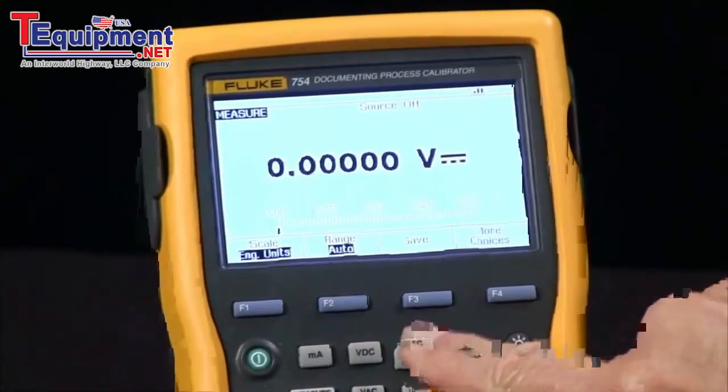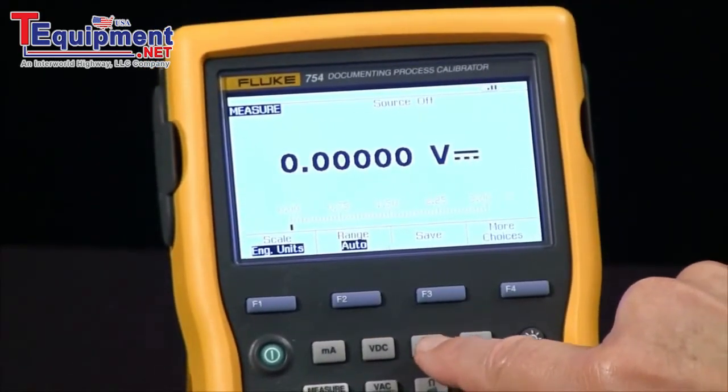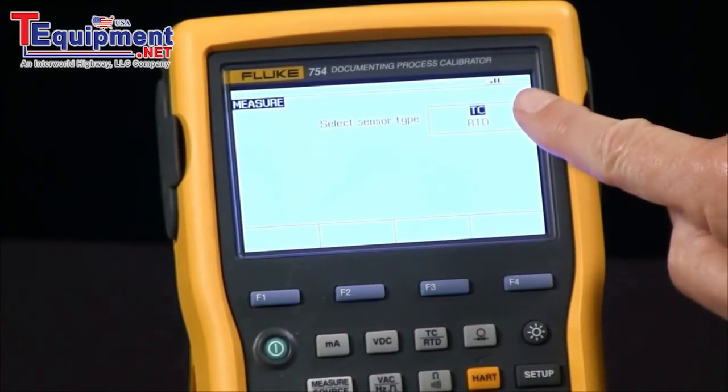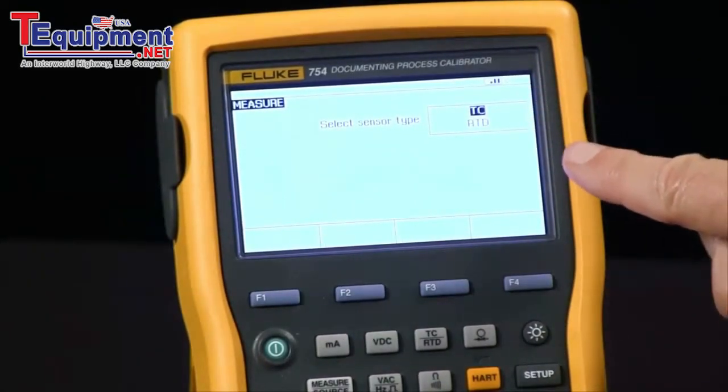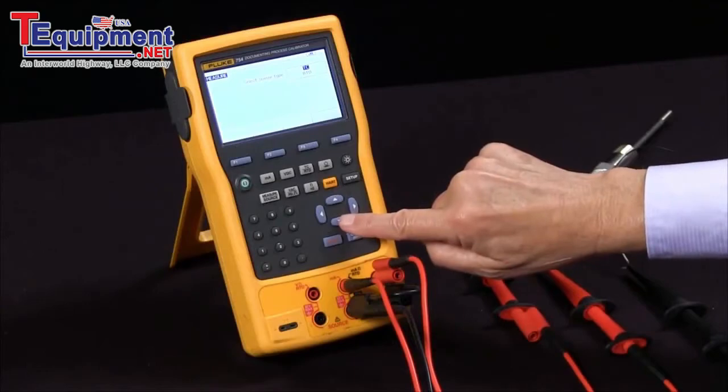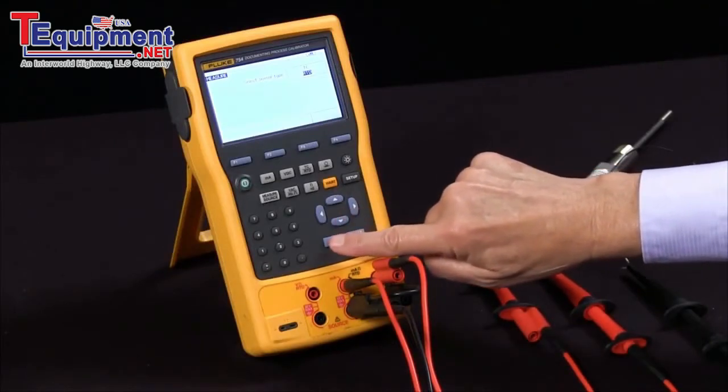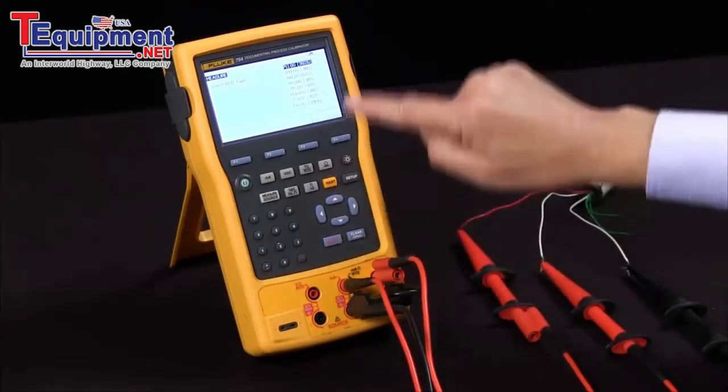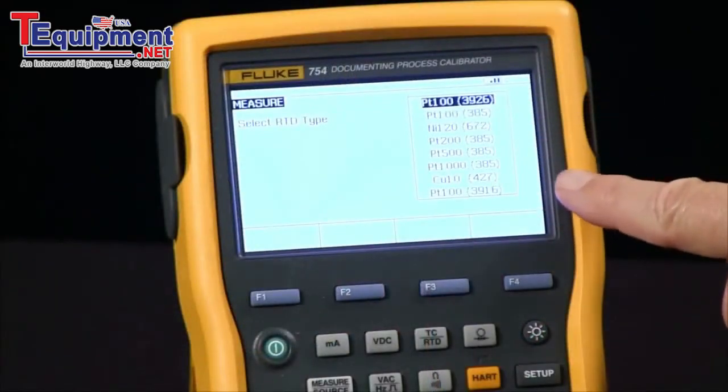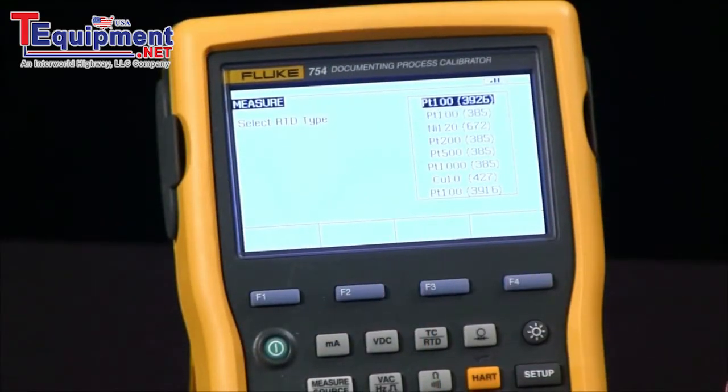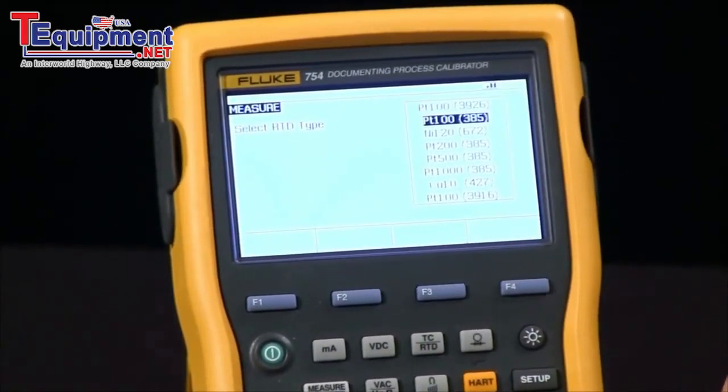All we have to do is push the thermocouple RTD button and we get a choice of thermocouple or RTD. I'm going to arrow down, highlight RTD, and hit enter. Then we get a choice of different types of RTDs. I'm going to select platinum 100 ohm.